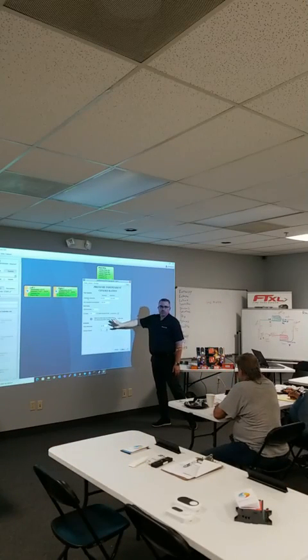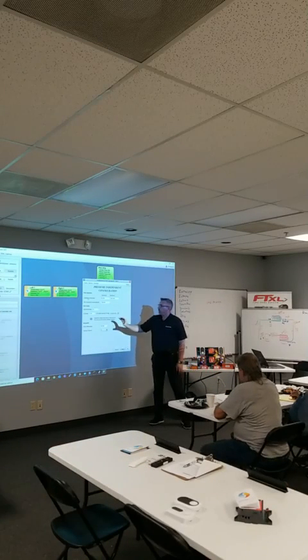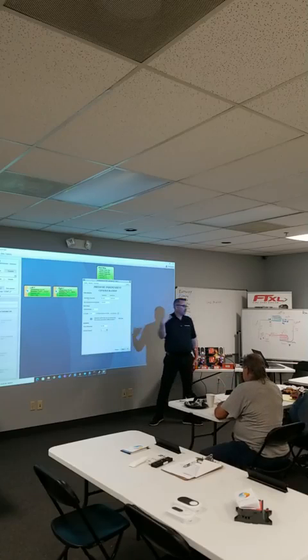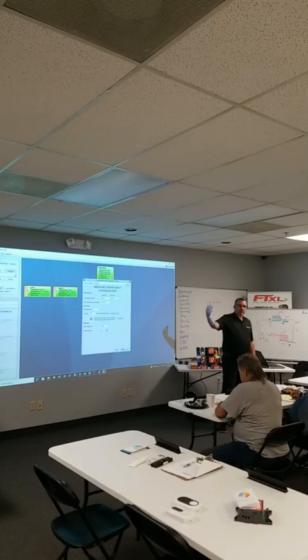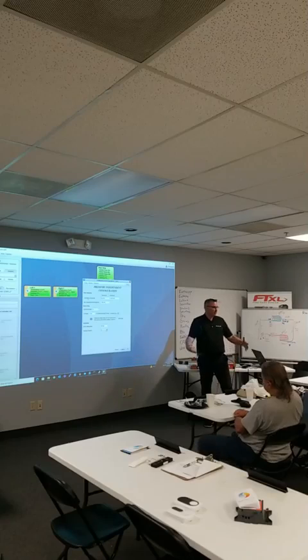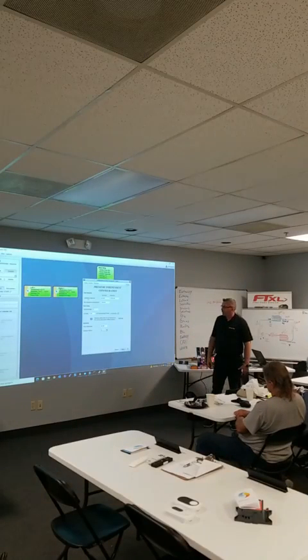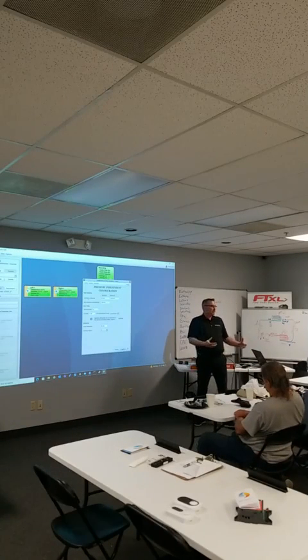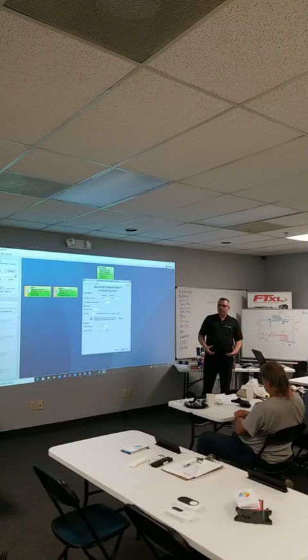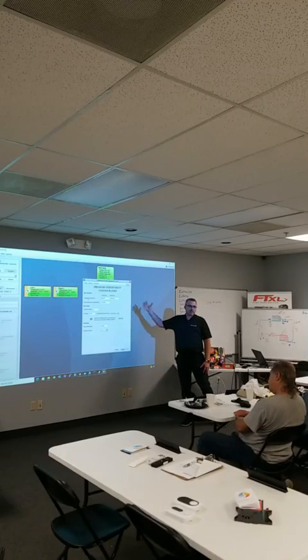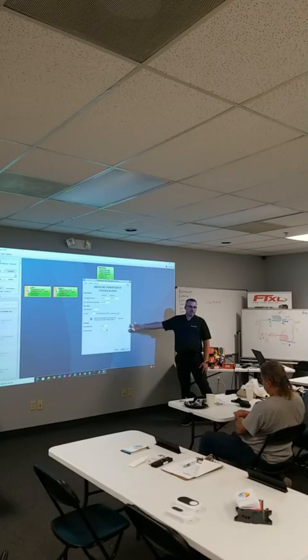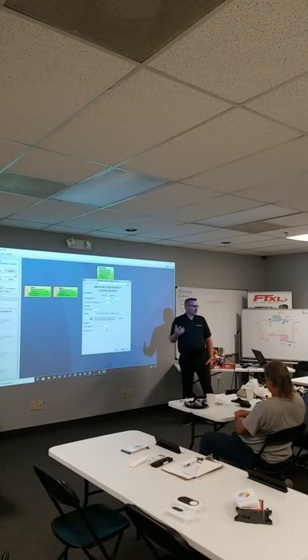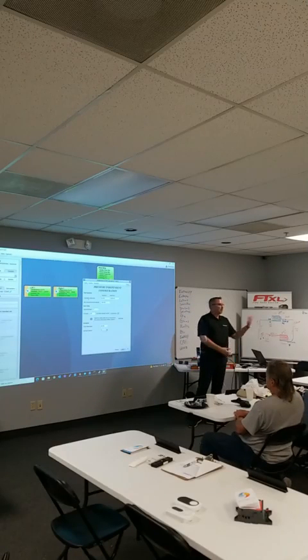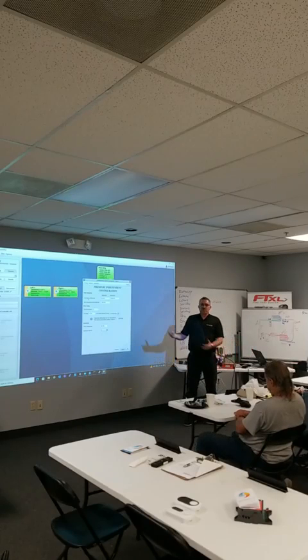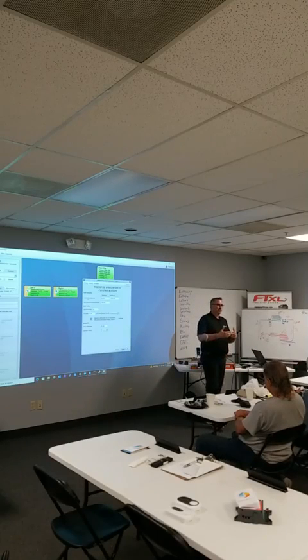Something to know, because it's a good question you asked, out of the box, sometimes people get concerned who never worked a lot with VAV, and like I said, our focus is HVAC mechanical service contractors. Because it is velocity pressure and we're converting it to CFM, if you leave this as an 8-inch box default out of the box until someone else can get to it to change the settings, the box is still going to try to control. It's going to see cooling demand and try to open the damper, it's just going to be more air, but essentially, you have to think of it like this.